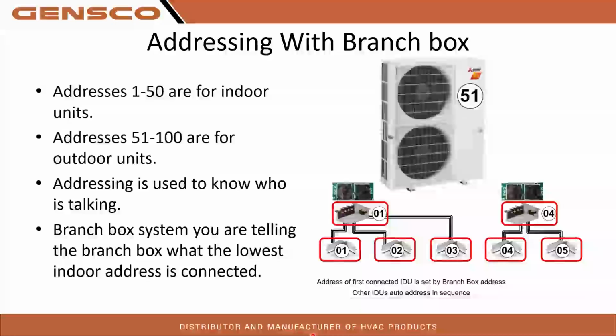Addressing. So whether you're using a branch box or smart multi or City Multi indoor equipment, anytime you have a smart multi heat pump, you do have to set up addressing. So the way that address structure works is addresses 1 through 50 are reserved for indoor units. 51 through 100 are for outdoor units. So if you're having multiple heat pumps tied to one system, that's why we have a whole wide range for that.